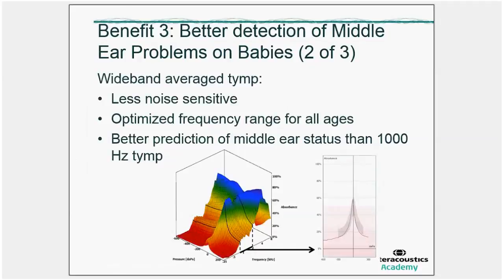The second benefit on babies is the use of the wideband averaged tympanogram. When babies are tested with 1000 Hz, very often the curve is difficult to make an interpretation of, particularly if the baby is not fully cooperative. With an averaged measurement, there is less noise. And the frequency range of this measurement is optimized to differentiate best for babies. And it is reported in literature that the predictive value of the wideband averaged tympanogram is much higher than for 1000 Hz tympanograms.